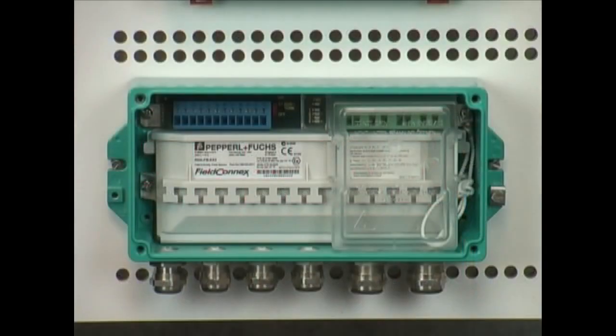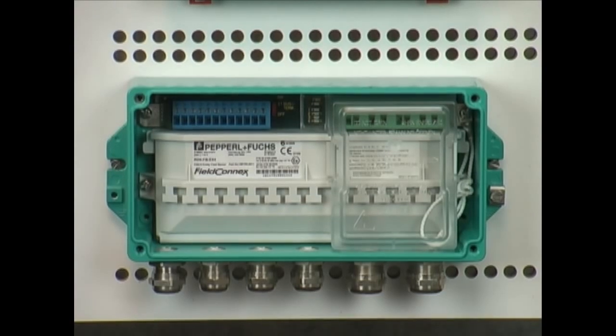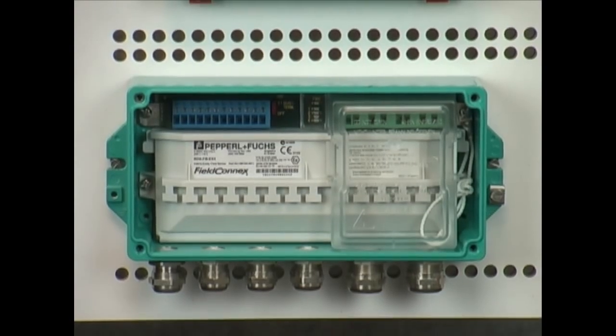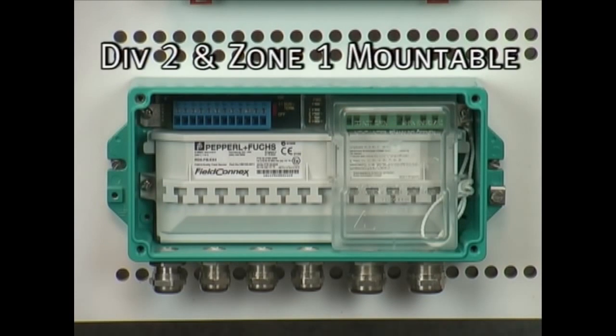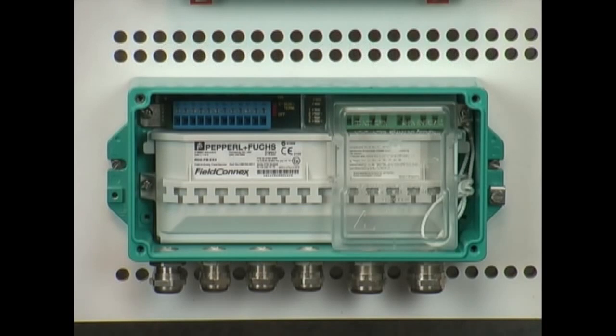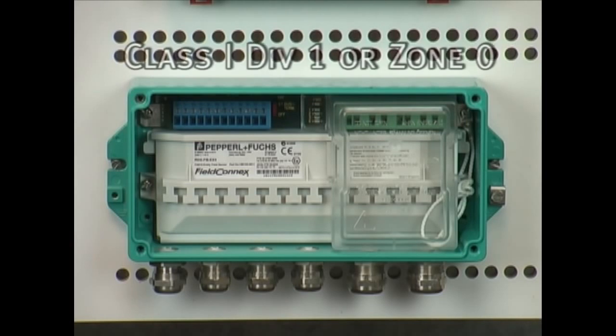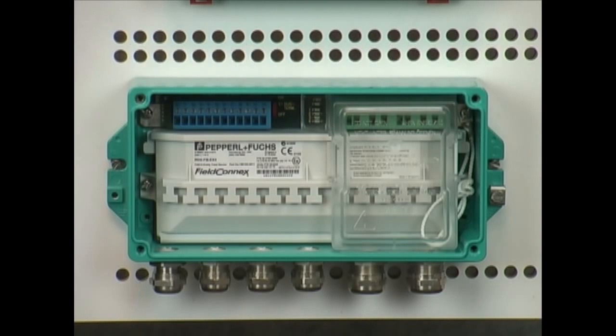Another option for field distribution when using the high power trunk concept is the field barrier. This is a division two mountable, zone one mountable interface that provides you with four intrinsically safe outputs for use in class one div one or zone zero applications. It provides again short circuit protection for the individual spurs as well as the optional terminator.